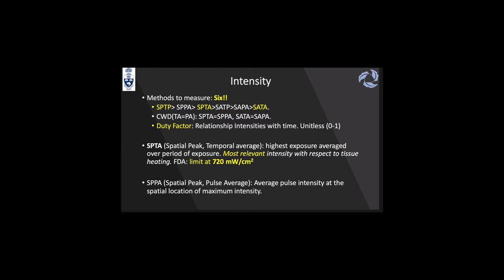The Spatial Peak Pulse Average (SPPA) is the average pulse intensity at the spatial location of maximum intensity. To summarize: Spatial Peak Temporal Peak (SPTP) is the highest intensity of all; Spatial Average Temporal Average (SATA) is the smallest intensity of all; and Spatial Peak Temporal Average (SPTA) is the most relevant intensity with respect to tissue heating. The duty factor is the relationship between intensities with time — it is unitless and goes from 0 to 1.